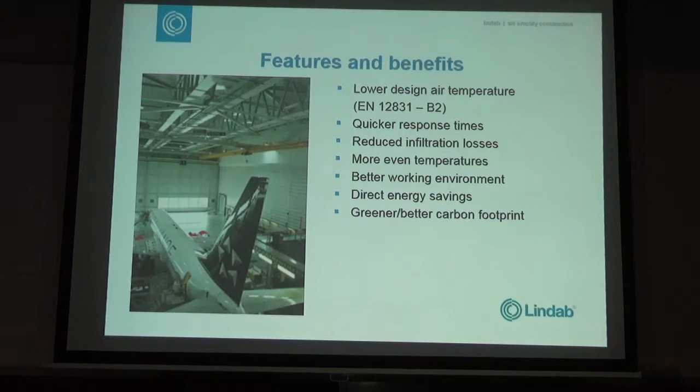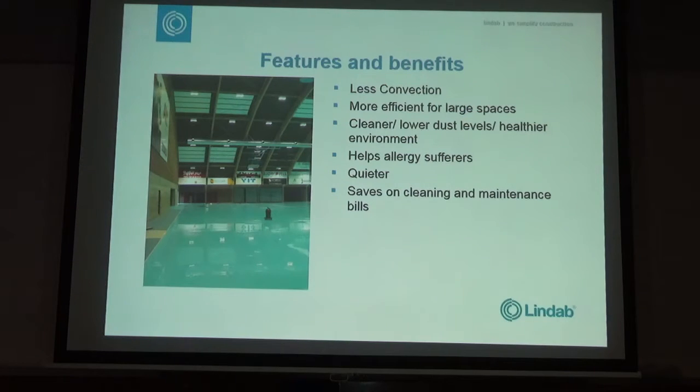And then a bit at the end, direct energy savings and a better carbon footprint. If you take into account resultant temperature, 3 degrees lower than air temperature, and you take into account five minute warm-up time instead of a 60 minute warm-up time, then it reduces the size of your plant. And it reduces the amount of heat loss that you calculate, so then you reduce the size of your plant and your energy use. Just to say that 21 degrees air temperature against 18 degrees resultant radiant temperature has the same comfort levels, that's what the literature says about it.